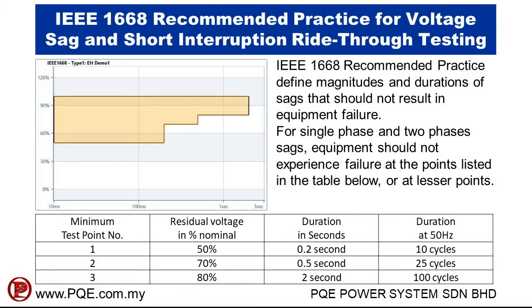IEEE 1668 recommended practice defines magnitudes and durations of sags that should not result in equipment failure. Equipment shall be able to withstand a 50% voltage sag for a maximum of 10 cycles, a 70% voltage sag for a maximum of 25 cycles, and an 80% voltage sag for a maximum of 100 cycles.